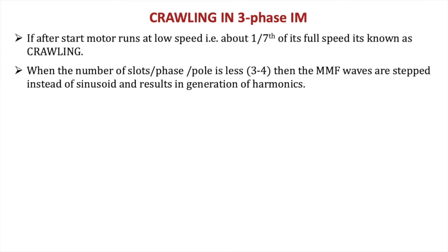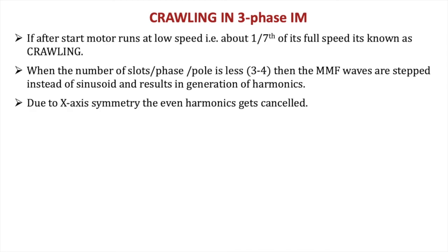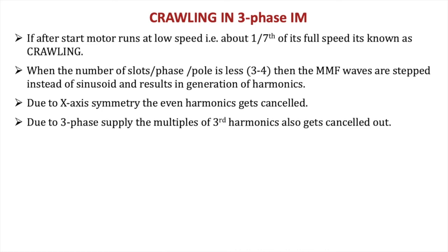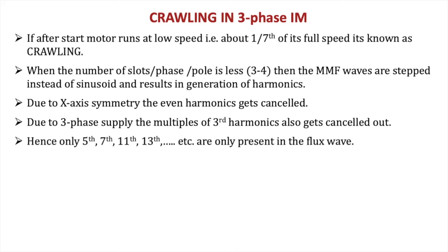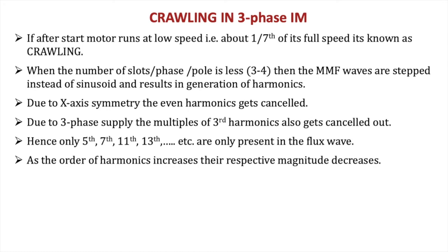When the number of slots per phase per pole is less than 3 to 4, that is, the number of slots provided for a single pole formation in the winding of the stator is less than 3 to 4, then the MMF waves, the magnetic fields produced by the given stator, are not sinusoidal and are in a stepped condition, and therefore generate harmonics. Due to the x-axis symmetry, the even harmonics get cancelled out. Because it's a three-phase supply, the multiples of the third harmonic also get cancelled out. So only the remaining harmonics are there, which are the 5th, 7th, 11th, 13th and so on. As the order of harmonic increases, their respective magnitude decreases. So the maximum will be the 5th harmonic, then the 7th, 11th, 13th and so on.